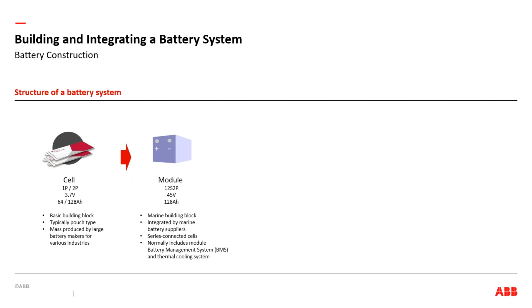Once those cells are stacked together, that's called a module, which becomes the basic marine building block—the lowest voltage increment you can size your system with. In this example, we're saying 45 volts. The module is critical because it's built by the battery manufacturer and has integrated battery management system components and cooling system components. Thermal management on batteries is really critical both to safety and longevity. These series-connected cells form the module, and once you stack modules together, you put them into a string, also known as a rack or a pack.